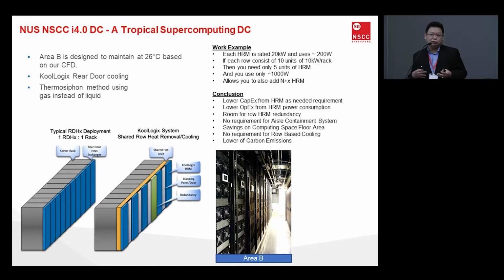You may not want to spread it; you may want to put some high density machines in certain racks. So this is where we get the advantage, because it's shared. In the event that you do not use as much, you don't need to use one whole row of 200 kilowatts. It is possible, based on design, for some of the doors to be just blanking panels instead. So you reduce the amount of rear doors that you have, because each rear door takes away about 20 kilowatts. It really depends on what you need. So this gives us flexibility, hence lower capex in terms of the HRM system. This is an actual photo of area B where we installed the system.